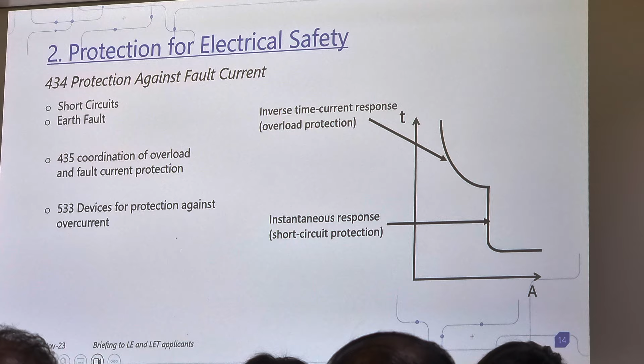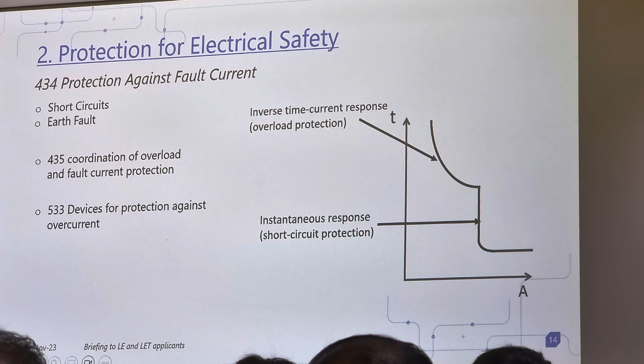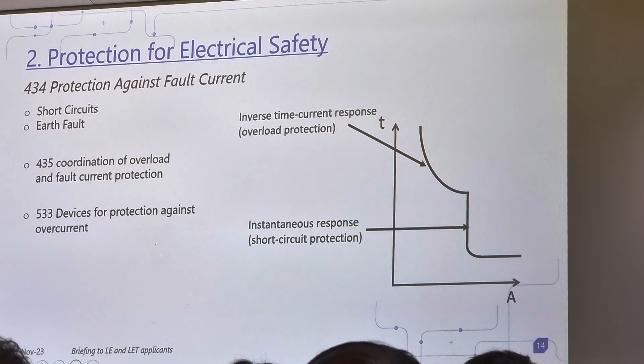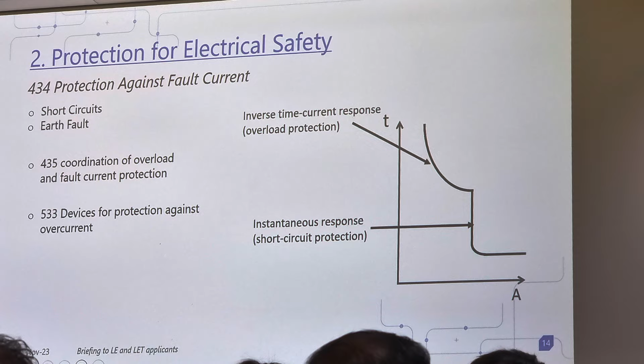MCB, we have upstream, other MCCB, for example. So all these need to be coordinated. You may even want to use fuse, depends on the installations. Of course, the company asks to tell you if the fault level is afforded by backup fuse, probably you can do a fuse protection. So what are the devices that we use for protection against overcurrent?